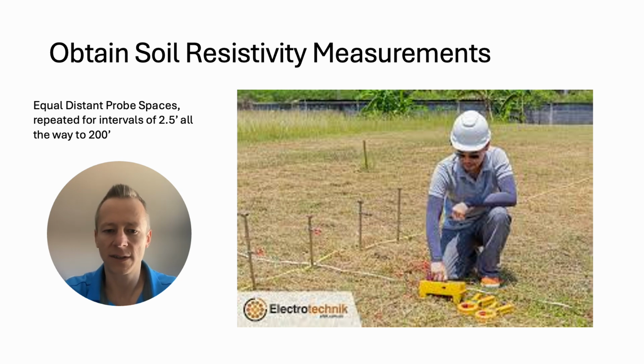And then oftentimes you have some risk if there's metallic objects buried in the soil that they'll throw your measurements off. So a lot of times to work around that, you'll take a perpendicular. You'll do your first set of measurements where you string out your line and you'll increase your probes along that line, and then you'll start over and rotate your test 90 degrees and go perpendicular to your first test. That way, if you were overly skewed in one direction, hopefully you're no longer parallel with it, and it'll skew your other set of measurements much less.